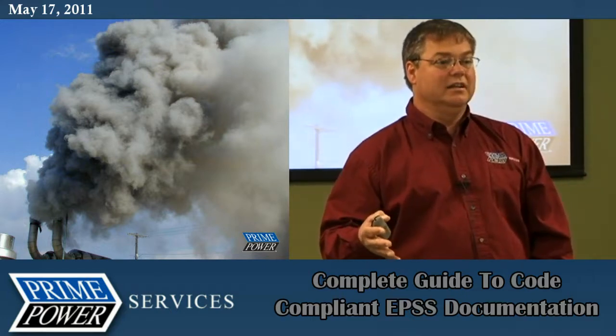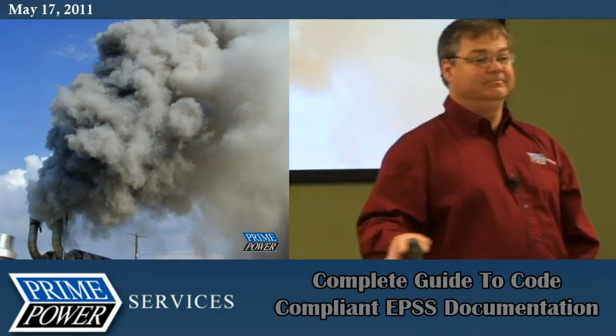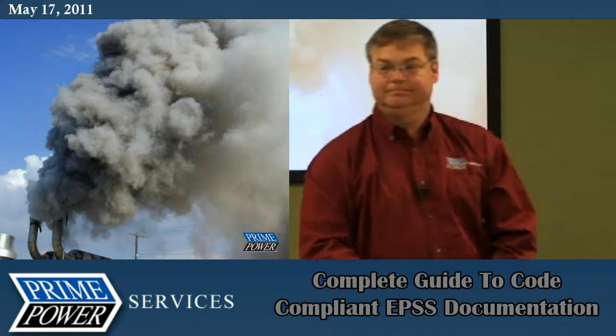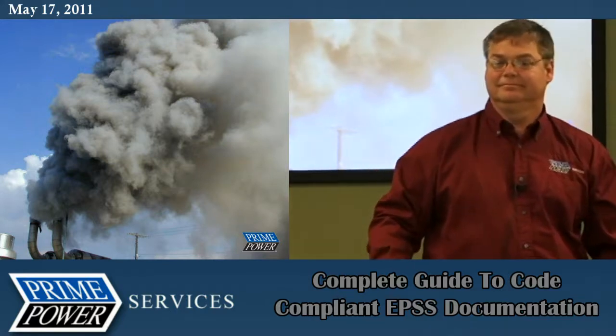What is Joint Commission's requirement? There is no requirement for a weekly test from Joint Commission at all. Monthly, yes. Most manufacturers say run it up to when it reaches peak temperature.